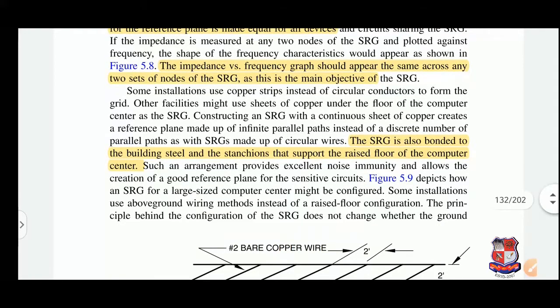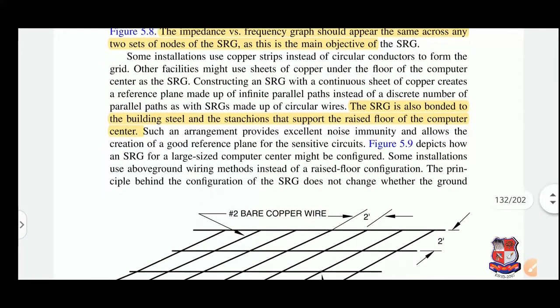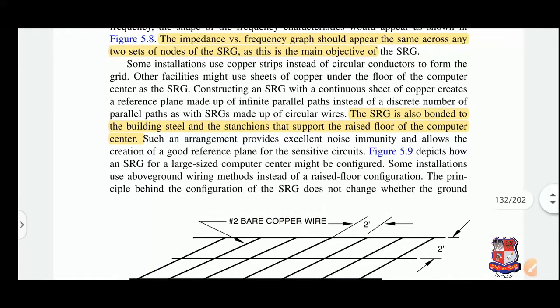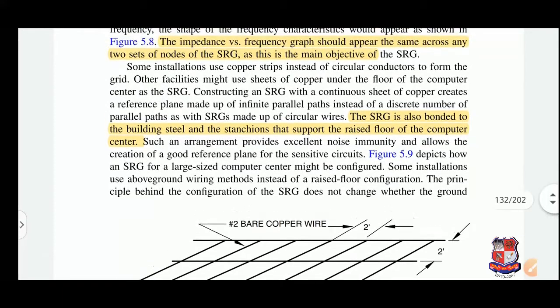Some buildings may prefer copper strips instead of circular conductors to form the grid; other facilities might use sheets of copper under the floor of the computer center. The arrangement may vary according to requirements. Constructing the SRG with a continuous sheet of copper creates a reference plane made up of infinite parallel paths, as opposed to a fixed number of parallel paths with an SRG made up of circular wire. The continuous copper sheet covers the whole area, creating far more parallel paths.